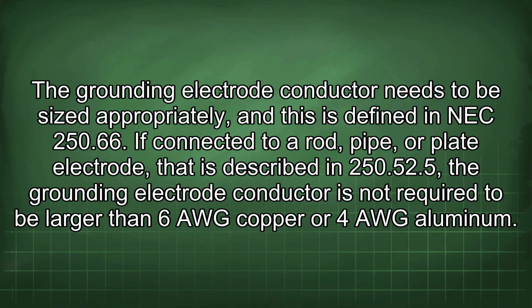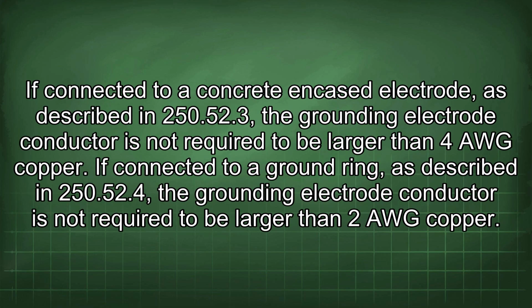If connected to a rod, pipe, or plate electrode that is described in 250.52.5, the grounding electrode conductor is not required to be larger than 6 AWG copper or 4 AWG aluminum. If connected to a concrete encased electrode, as described in 250.52.3, the grounding electrode conductor is not required to be larger than 4 AWG copper. If connected to a ground ring, as described in 250.52.4, the grounding electrode conductor is not required to be larger than 2 AWG copper.